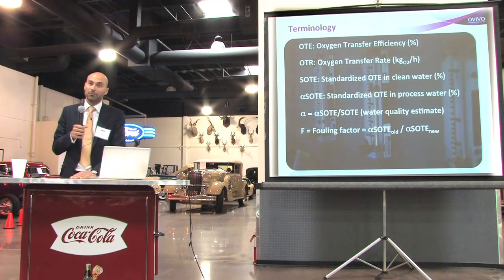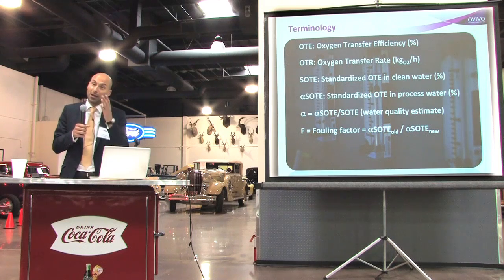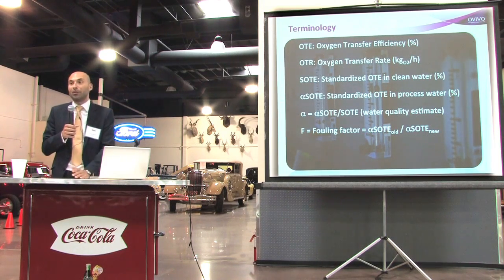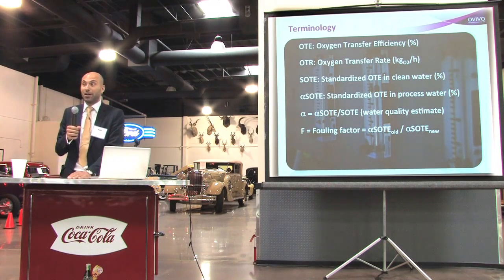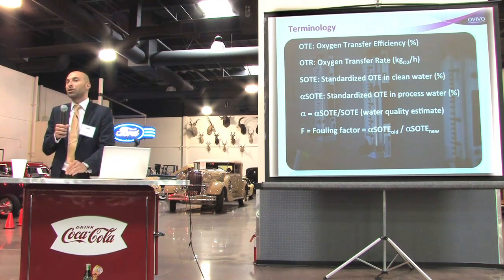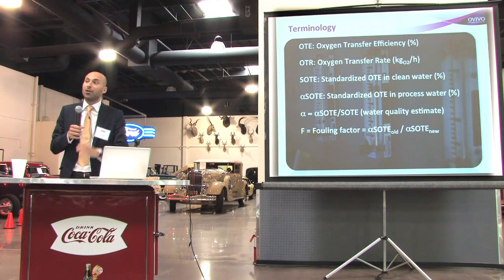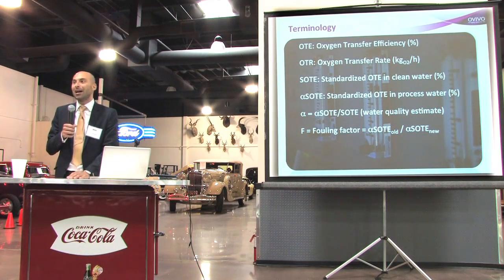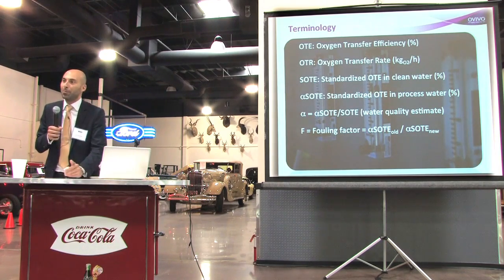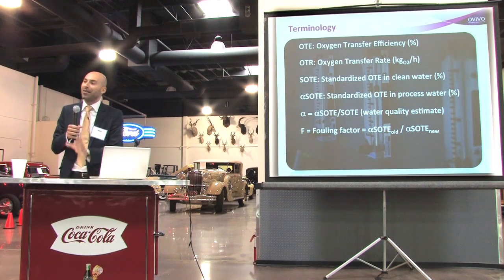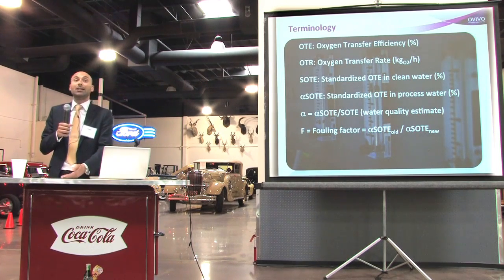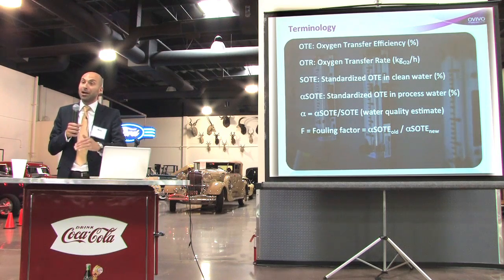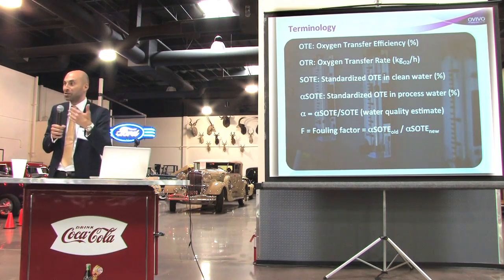The ratio of the current alpha value to the initial value is called the fouling factor f, which starts at 1.0 by definition and can decline over time. When you design or own a system, it must be sized not just for day one but to last for years — because if efficiency drops significantly in two years, your power bill will go up, and you may also lack the capacity to supply enough oxygen to meet treatment needs.